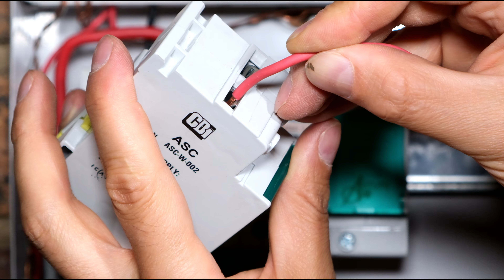Notice the wire goes in there, but the protective covering does not go in there. So I never tighten onto the jacket, I only tighten onto the copper. So from the output of the circuit breaker, we go to the live input of the timer, which is there at the top. Now, what size wire you should use depends on the circuit breaker.